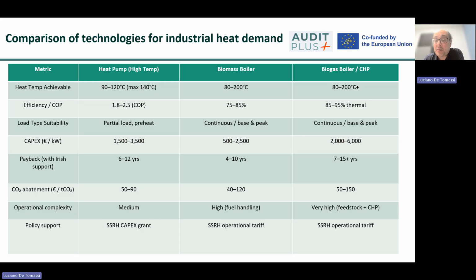Biogas boilers and CHP systems typically deliver heat in the range of about 80 to 200 Celsius degrees, with CHP systems also producing electricity alongside heat. Overall system efficiency for CHP can be very high, often 80 to 90% total energy utilization when both heat and power are effectively used, although electrical efficiency alone is typically around 30 to 45%. These systems are best suited to continuous heat demand where there is also a beneficial use or export route for electricity, making them particularly valuable in industrial sites with stable baseload demand and grid connection capacity.